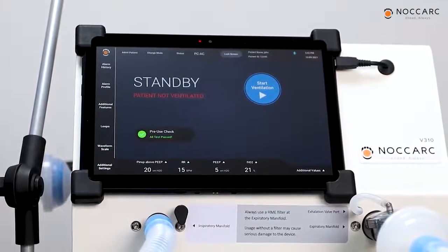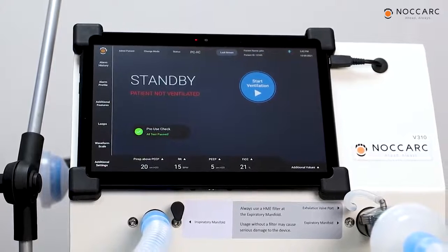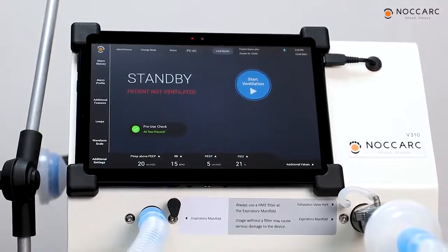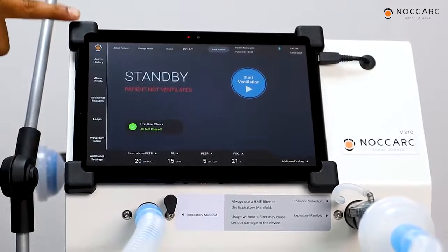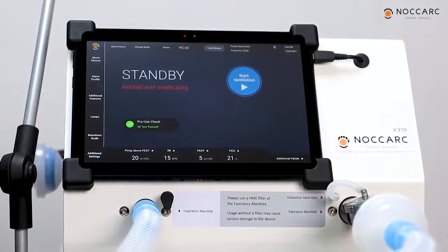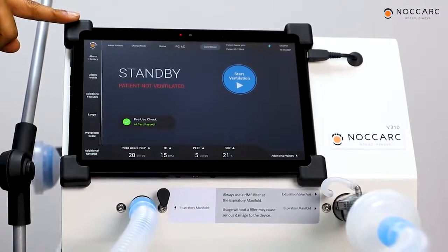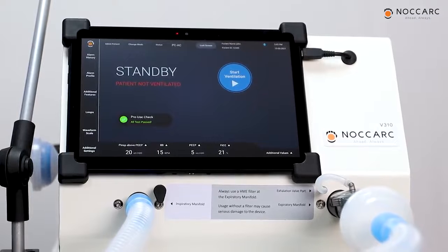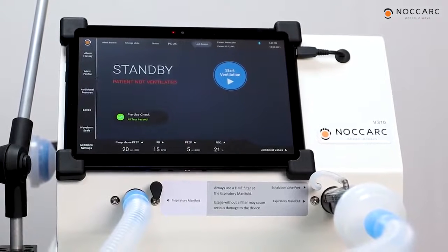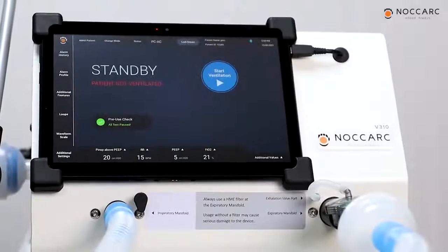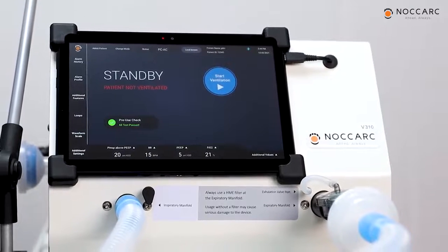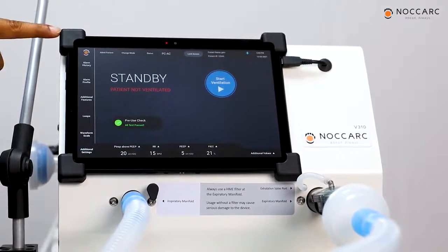While keeping V310 on standby, if the user only switches off the ventilator switch and the UI screen is not turned off, in that condition, the battery of the UI screen will be discharged. It results in slow working of the UI screen when the ventilator is used next time. For that reason, the user always needs to ensure that the UI screen and the ventilator switch are in off condition while keeping V310 on standby.